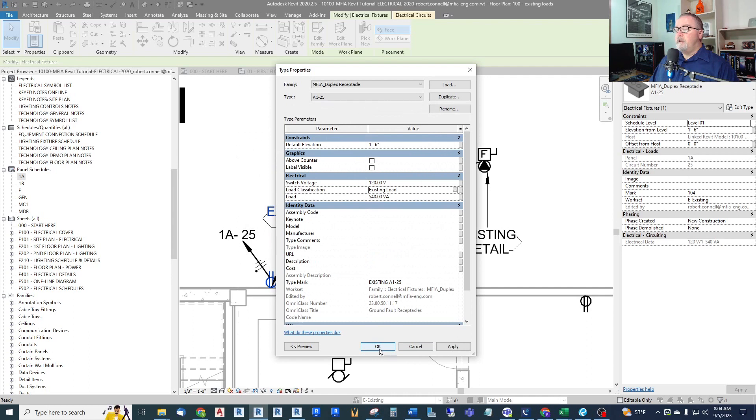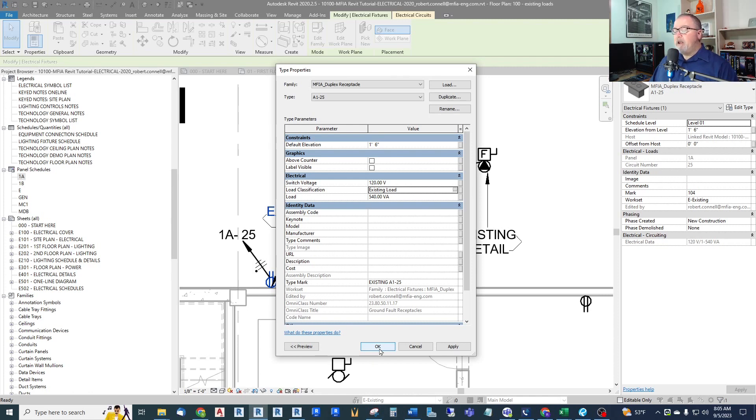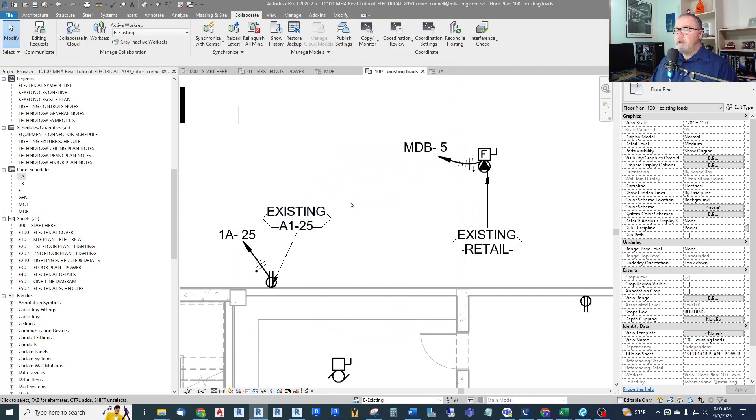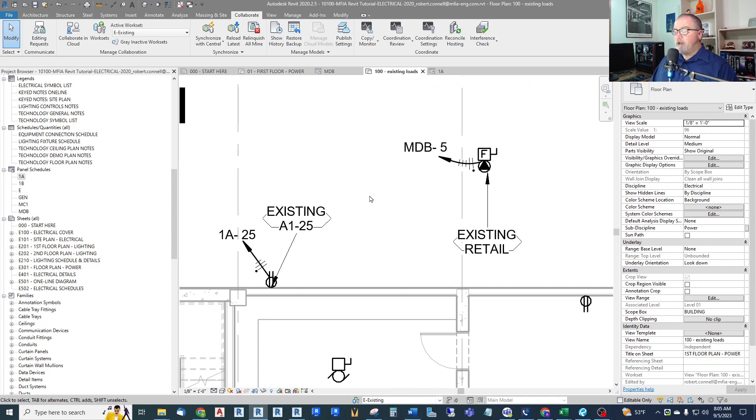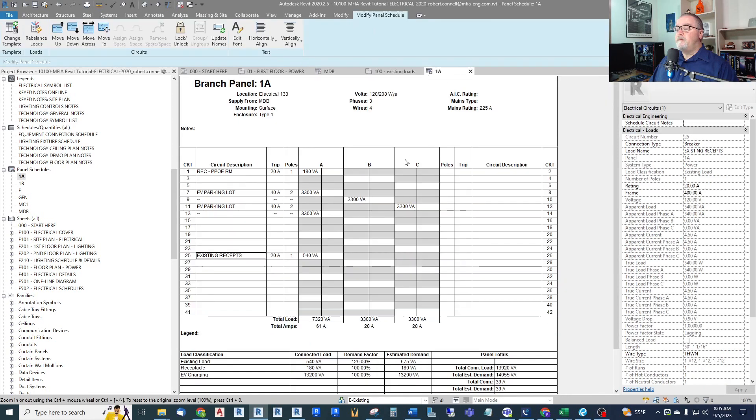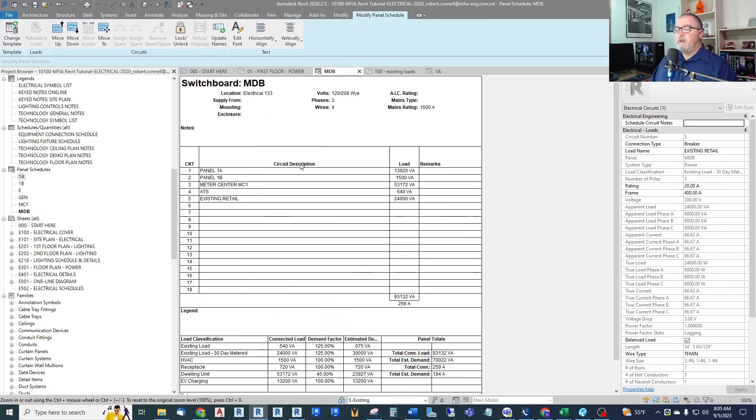I can just call this existing load. Now, if I want to try to take my existing receptacles and apply 10K of, you know, the first 10K at 100%, the second at 50, I could do all that. But typically, I'm just going with connected loads on these. So that's how that works. And again, it does not show up because I'm doing this all in the existing work set. It does not show up here. It only shows up in my panel. Existing load. And it will also show up in MDB as existing load and carries through the entire system.